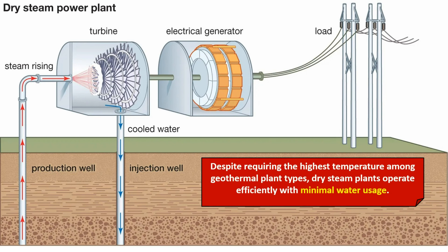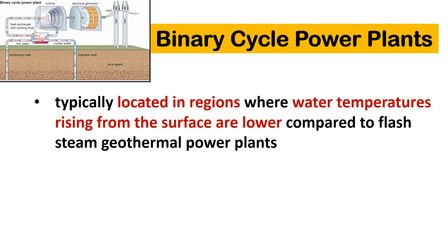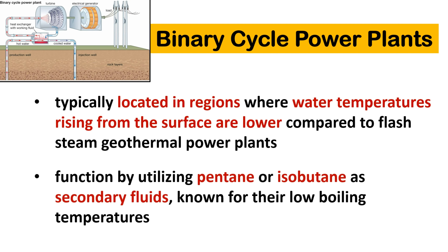Despite requiring the highest temperature among geothermal plant types, dry steam plants operate efficiently with minimal water usage. Binary cycle power plants are typically located in regions where water temperatures rising from the surface are lower compared to flash steam geothermal power plants. They function by utilizing pentane or isobutane as secondary fluids known for their low boiling temperatures.